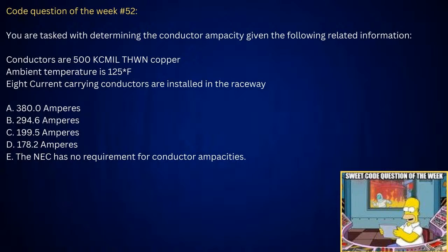But he's tricking you here. He's using THWN, so that's your 75 degree C column. Now, when you do that, I'm going to go over and look at Table 310.16. Let me get my calculator out because I'm going to have to calculate this. I don't know this off the top of my head. So I come down, I pick up 75 degrees C, and I pick up 500 kcmil in Table 310.16. It's going to tell you it's good for 380 amps. All right? You can see how I threw that in there as one of the answers, so people thought they were done right there. Yeah, you ain't tricking me on that stuff.